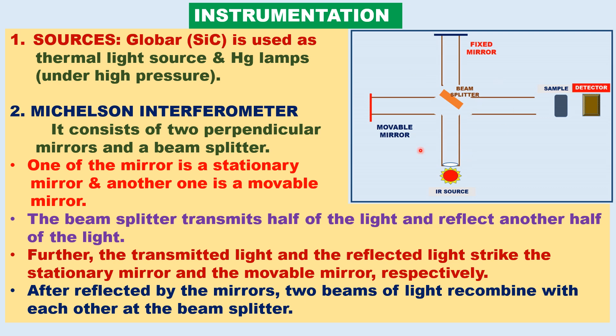Let us now see the instrumentation. This is the schematic of the FTIR spectrophotometer. It consists of an IR light source. A Globar is used as a thermal light source — it is made up of silicon carbide. By heating silicon carbide, it emits IR radiation. Alternatively, mercury lamps under high pressure can be used.